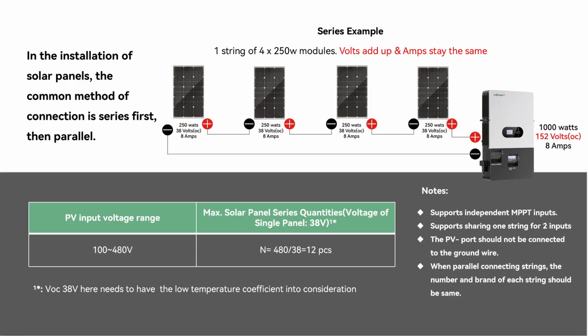Then we can calculate how many solar panels we can connect in series per string. As you can see here, the maximum PV input voltage is 480 volts divided by 38, which means 12 pieces. So we can connect 12 pieces in series per string, just by the voltage. And if the installation site has a large temperature difference, we also need to take the temperature coefficient into consideration.